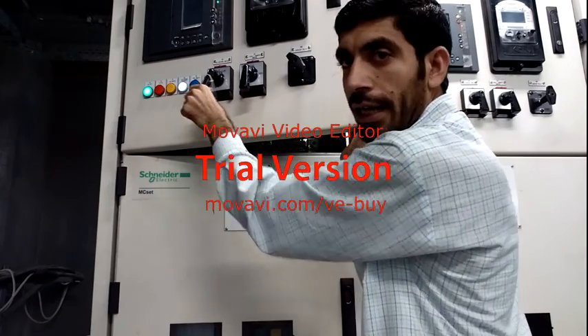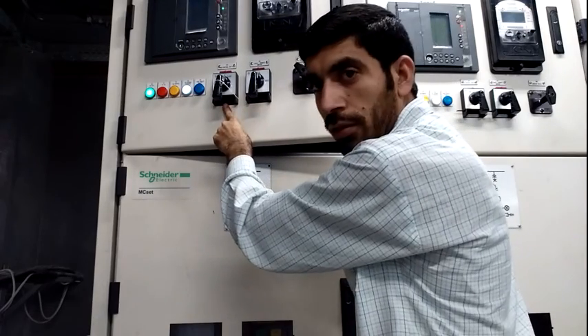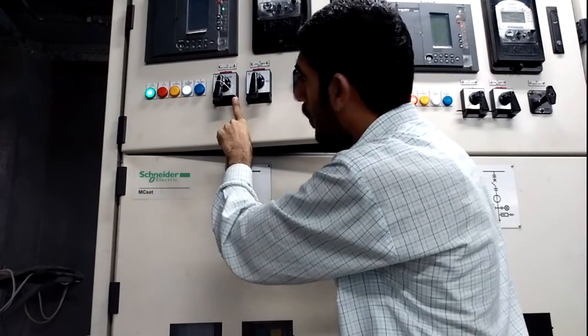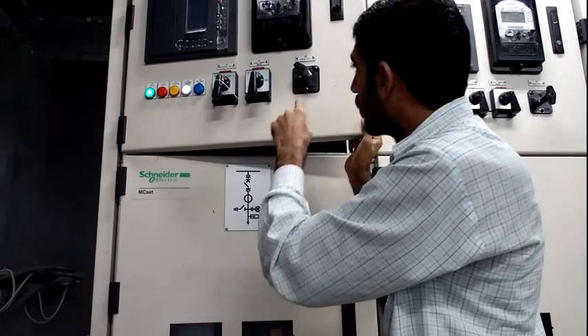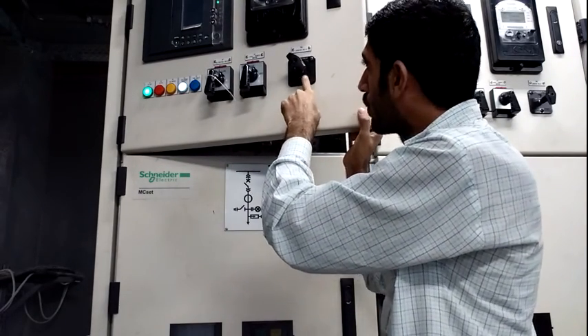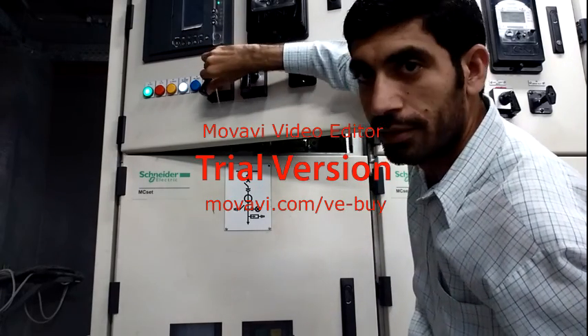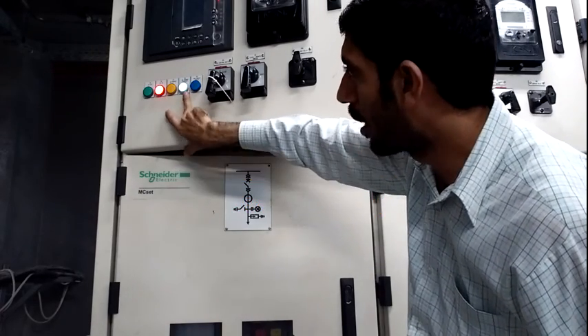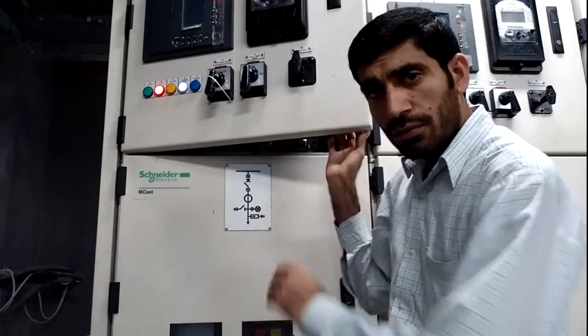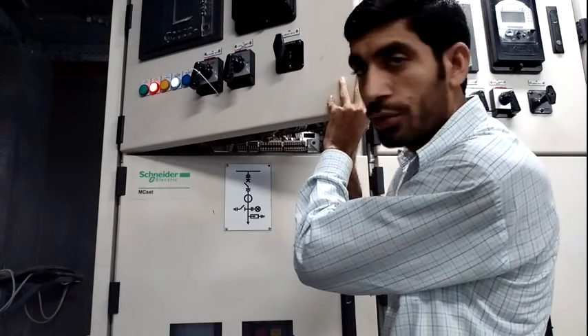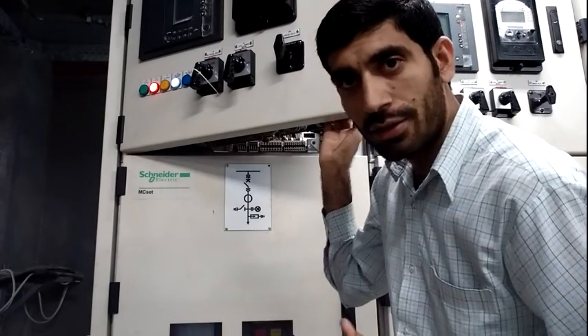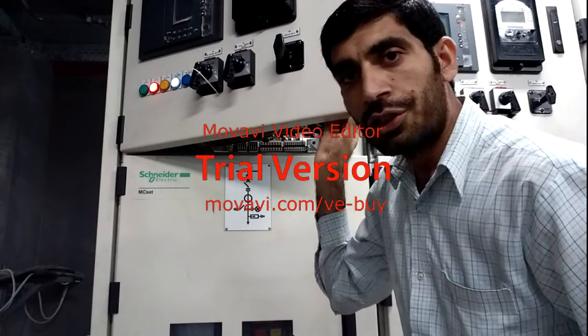When the lockout is operated, you cannot reclose the breaker. See, I cannot close the breaker. My lockout is in lock position, so I cannot close the breaker. When I reset the lockout relay, I can close the breaker. See, now the indication is glowing red. That means the breaker is closed and also charged. Now I retry to open the breaker through the lockout relay. As the lockout relay is operated in earth fault or short circuit condition, my breaker will open and I cannot reclose it.